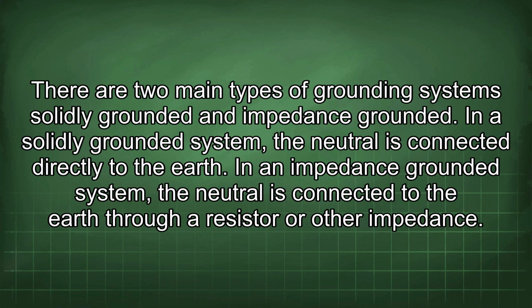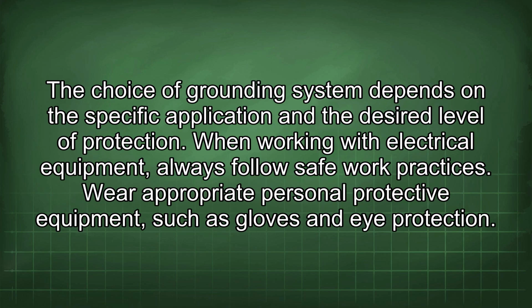There are two main types of grounding systems: solidly grounded and impedance grounded. In a solidly grounded system, the neutral is connected directly to the earth. In an impedance grounded system, the neutral is connected to the earth through a resistor or other impedance. The choice of grounding system depends on the specific application and the desired level of protection.